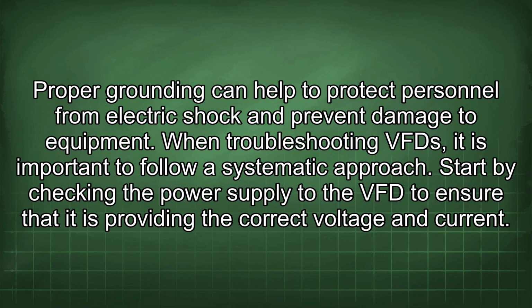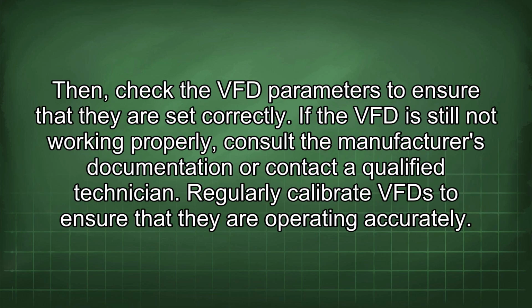When troubleshooting VFD, it is important to follow a systematic approach. Start by checking the power supply to the VFD to ensure that it is providing the correct voltage and current. Then check the VFD parameters to ensure that they are set correctly. If the VFD is still not working properly, consult the manufacturer's documentation or contact a qualified technician.